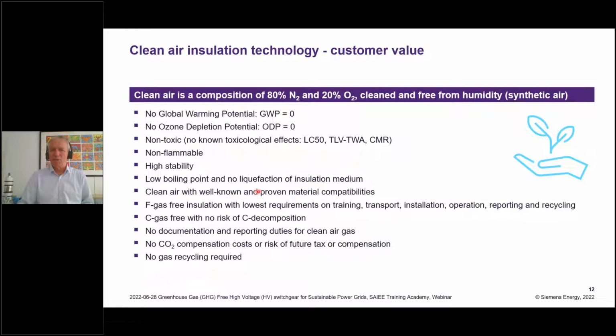It's well known. It has proven material compatibilities. It doesn't have F-gas in it, and therefore has the lowest requirements for training, transport, installation, operation, reporting, and recycling. It doesn't have C in it. Whenever you have C in the gases and you put energy to it, soot is generated, and soot is a conducting substance which we want to prevent. So there is no documentation and reporting duty related to clean air gas.